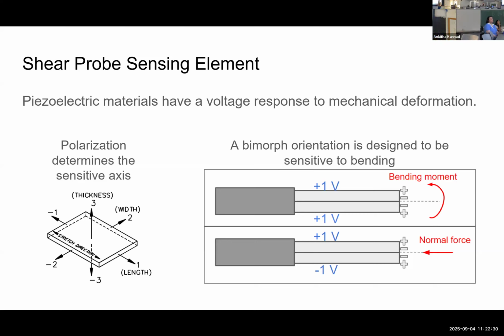Okay, so you have a piezoelectric material, and the thing that determines the axis that you're measuring, so the sensitive axis, is polarization. So by subjecting this material to a very strong electric field, you can determine how the molecules are oriented. And that is why it's called polarization, because you want the molecules all to be rotated in the same way. And it's defined based on the axes of the material. So if you have like the 3, 2, and 1 axes, for example, the way an ADCP is oriented is that you apply a voltage across the 3 axis and you want a deformation in that same axis. So if you picture having this cylinder and you want a sound wave to come straight out the face of that cylinder, it's polarized so that they apply a voltage across both sides of the face, and then that is the same face that pushes on the water.